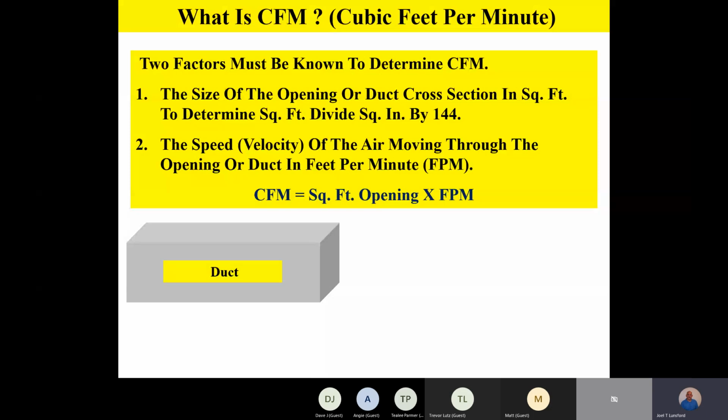Now remember, team, that maximum, you probably want to avoid when you design. Stay towards the lower end, at 725 velocity on the main trunk, and avoid those higher numbers so I have a nice, quiet, efficient system.